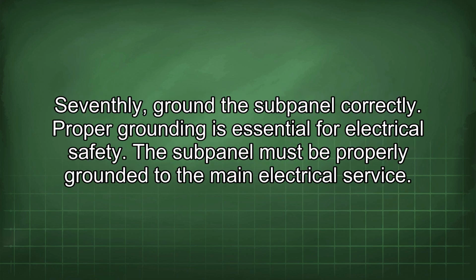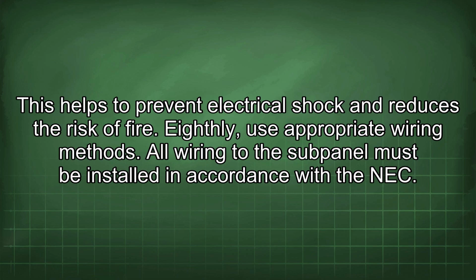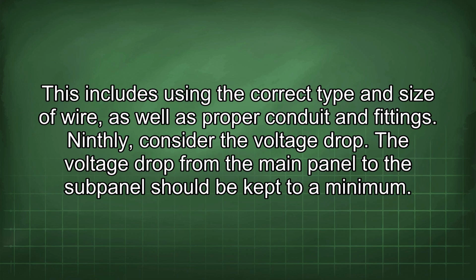Seventhly, ground the subpanel correctly. Proper grounding is essential for electrical safety. The subpanel must be properly grounded to the main electrical service. This helps to prevent electrical shock and reduces the risk of fire. Eighthly, use appropriate wiring methods. All wiring to the subpanel must be installed in accordance with the NEC. This includes using the correct type and size of wire, as well as proper conduit and fittings.